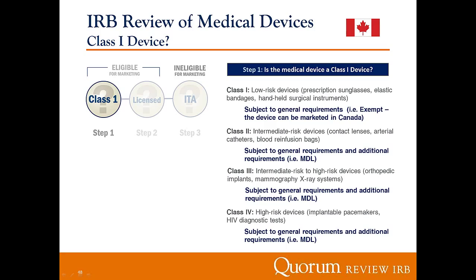You have class 3 devices. These are intermediate to high risk devices: orthopedic implants, mammography X-ray systems. These are subject to general requirements and additional requirements, those medical device license requirements. So again, class 2, 3, and 4 all require that medical device license from Health Canada. Finally, you have class 4. These are your high risk devices: implantable pacemakers, HIV diagnostic tests.